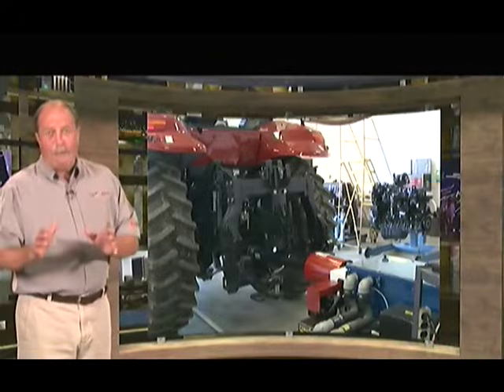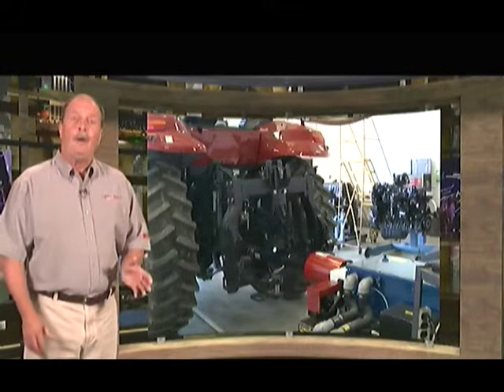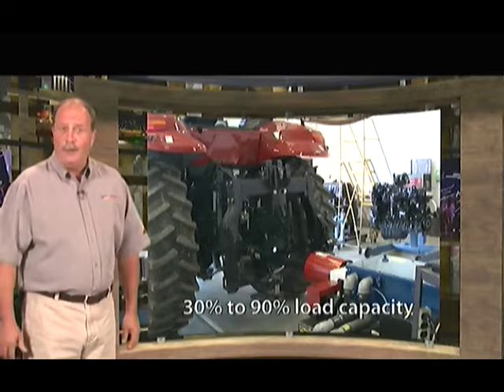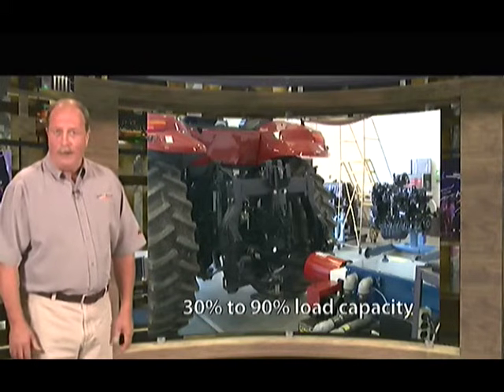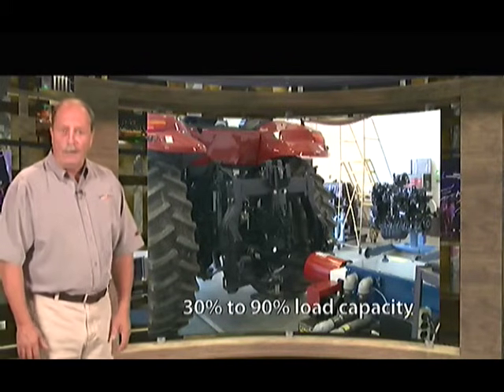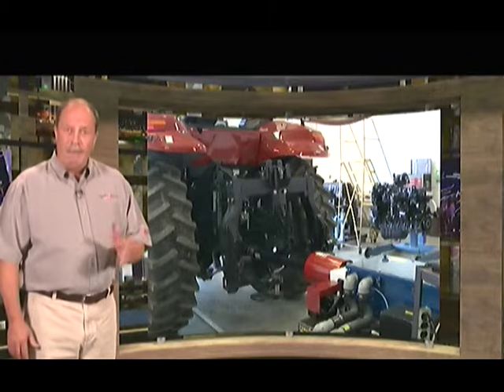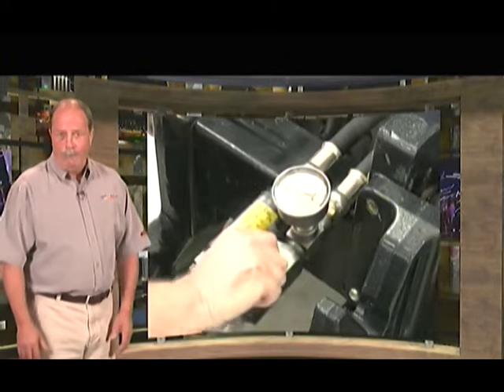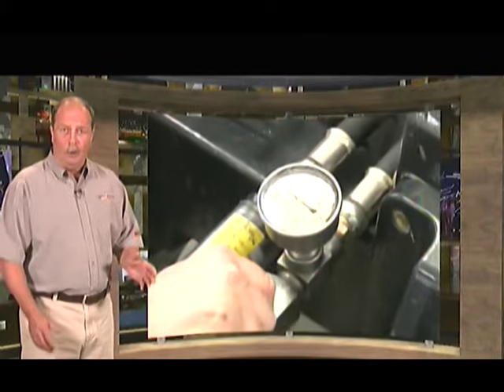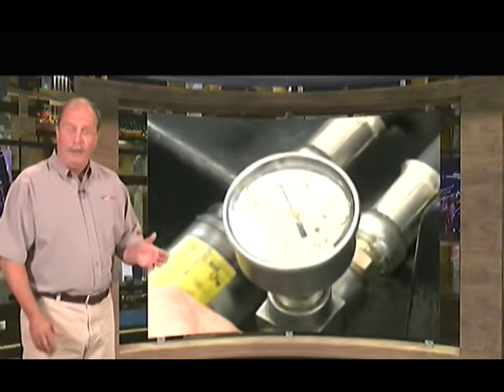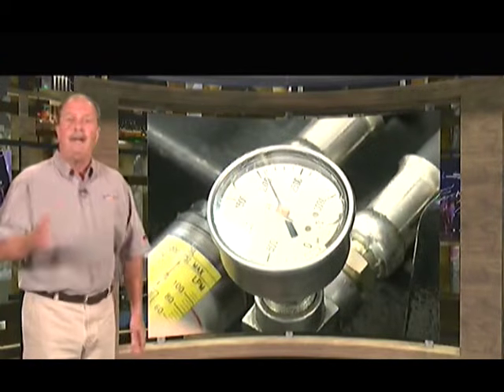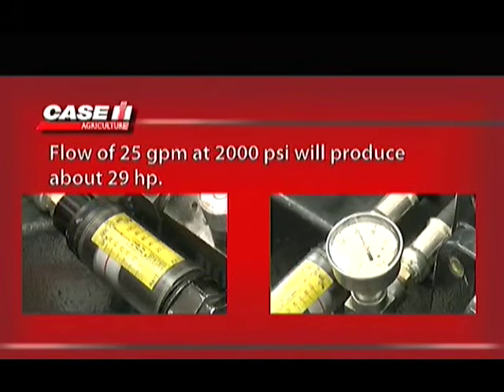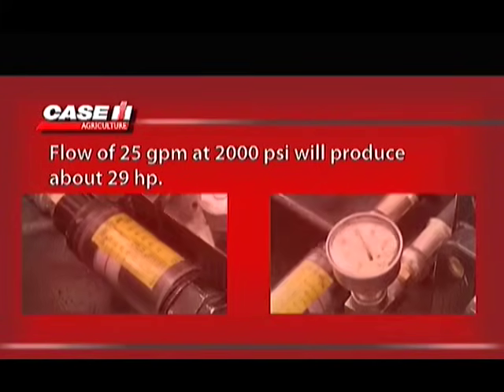To reach the proper exhaust temperature, place the unit under moderate to heavy load, a 30 to 90% load capacity via drawbar load or PTO dynamometer. Some units may be able to be loaded in high gear or placed under large hydraulic load in the remotes, using a flow meter and restriction. For example, a flow of 25 gallons per minute at 2,000 psi will produce about 29 horsepower. This is enough load to build adequate exhaust temperature.